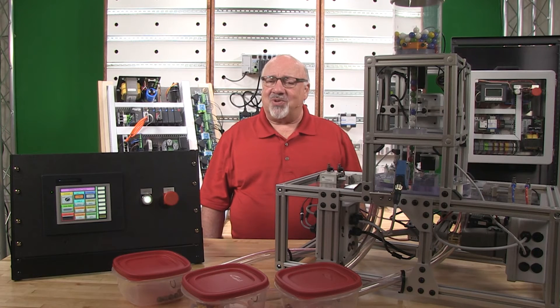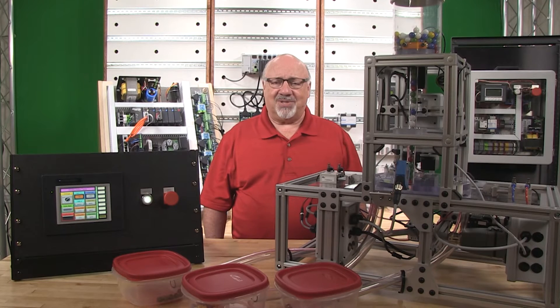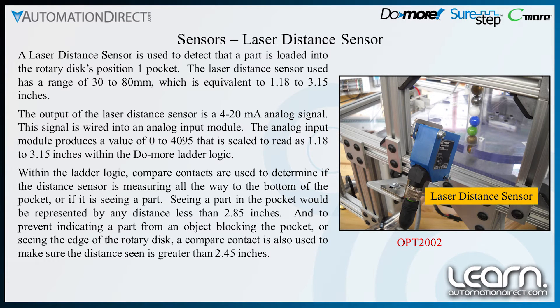A laser distance sensor is used to determine that a part has been loaded into the first position of the rotary disk. The laser distance sensor has been set up to show a sensing range of 1.18 to 3.15 inches. The output of the laser distance sensor is wired into a 4 to 20 milliamp analog input module. A value of 0 to 4,095 is produced in the DoMore PLC and is scaled to read 1.18 to 3.15 inches. Compare contacts used in the ladder logic determine if the distance reading indicates a part is loaded or if the pocket is empty.